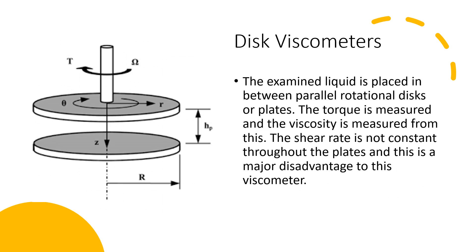Next, we have the disc viscometer. The examined liquid is placed between parallel rotational discs or plates, the torque is measured, and the viscosity is then calculated from that. However, the shear rate is not constant throughout the plates, and this is a major disadvantage of this viscometer.